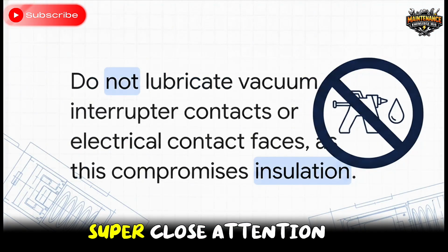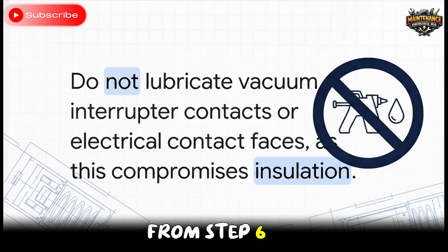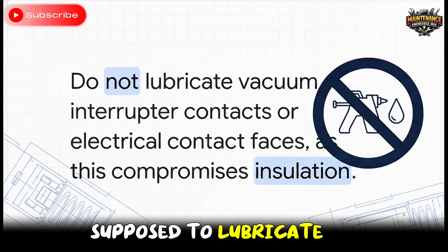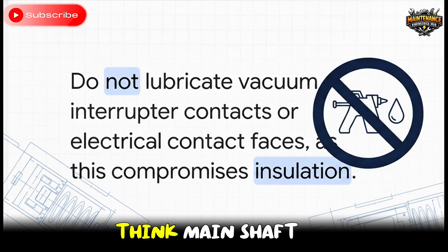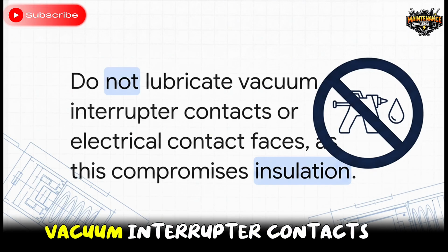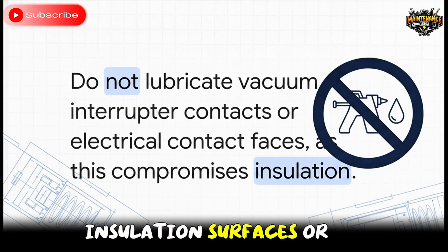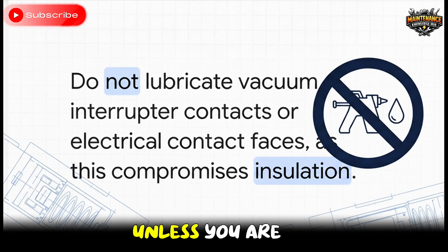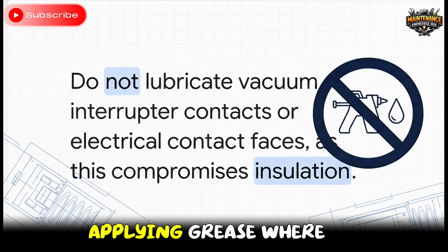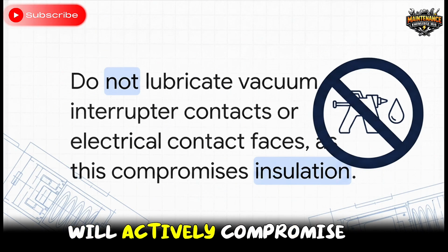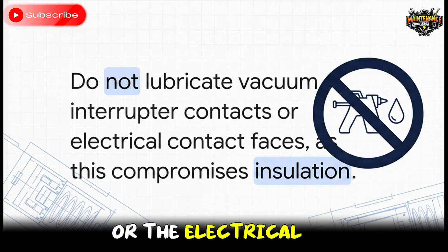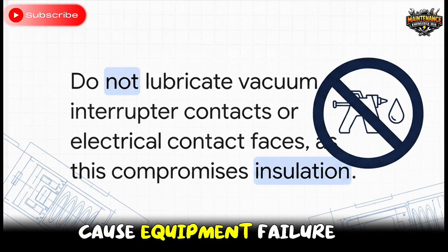But please, pay super close attention to this warning from step 6. You are only supposed to lubricate specified mechanical parts. Think main shaft bearings, hinges, rollers. Do not lubricate vacuum interrupter contacts, insulation surfaces, or electrical contact faces unless you are explicitly instructed to do so. So, the crucial point is, applying grease where it doesn't belong will actively compromise the insulation or the electrical connections, which will directly cause equipment failure.